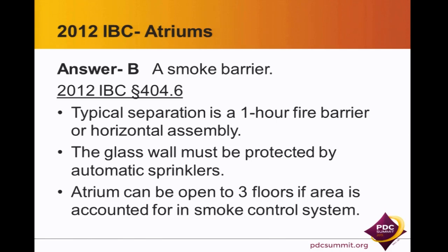I was doing a plan review recently, and it came up that the separation was not provided, and so they tried to say, well, we can just include all this area in the smoke control system. It was a great idea, except the smoke control system was already designed in size. So you really want to be mindful in your design process if that's going to be an option, because you'll essentially make your smoke control system useless.